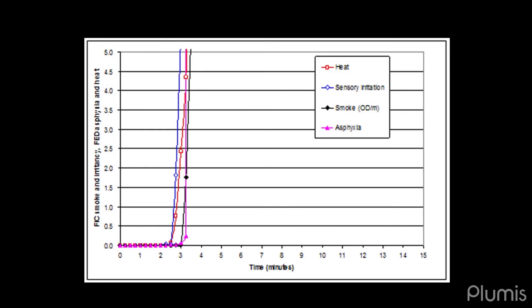Now, on this diagram here, what we're looking for is the time at which any of these curves, the curve for smoke, heat, sensory irritation or asphyxiant gases, the time when any of these curves crosses one on the y-axis. Because that is the calculated time at which each of these hazards reaches a critical level that would incapacitate the occupant and prevent them from escaping from the fire.